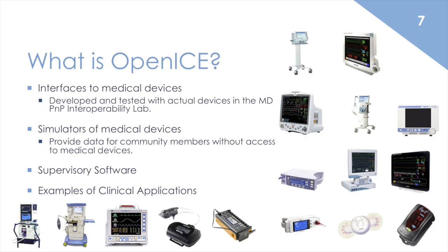The constituents of the platform include interfaces to myriad medical devices that are available in the MD PnP Interoperability Lab in Cambridge, Massachusetts. So in that lab, we've developed software to interface with a number of these devices, and we include those pieces of software as part of the platform. We also include software-based simulators of various medical devices, and this is for the use of those people out in the community who may not have direct access to medical devices.